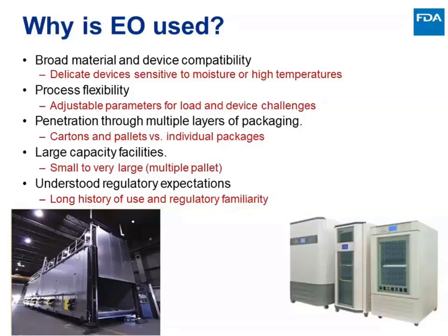The sizes that are being used now, though many hospitals are moving away from them, you see on the right side of your slide here. These are the kind of sterilization devices using ethylene oxide that you may see in a central supply setting in a hospital or outside of an OR, primarily to sterilize pieces that, for one reason or another, have become contaminated after delivery from the pre-hospital sterilization. I call your attention now to the one on the left, and that is that most of the supplies needing ethylene oxide for sterilization are pretty much anything that's not metal.